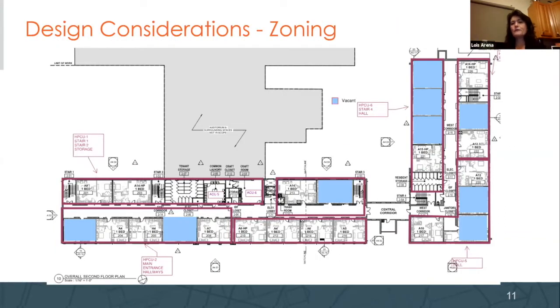Zoning. If you're going into heat mode without heat recovery and you're either going to be in heating or cooling and not the option to do both, you want to make sure you zone these floors properly. If you look at this, we are facing this wall here is facing southwest, this is facing southeast. South is this way. So you want to make sure you zone your apartments together.